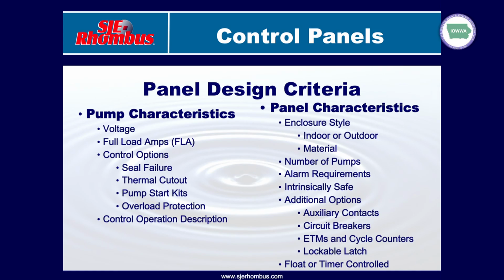Thermal cutouts can be incorporated into the panel if they're not already on the pump motor. And then pump start kits, overload protection, all of that can be incorporated into the panel. We just have to know ahead of time that that's required. Some of the panel characteristics that we're going to incorporate into the panel, the enclosure style, and generally most residential applications you're going to use a thermoplastic or a fiberglass control panel enclosure. We get into some commercial jobs, they may require stainless steel, painted steel, aluminum, things like that.